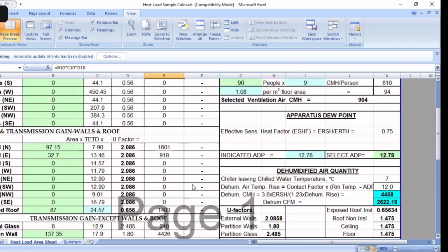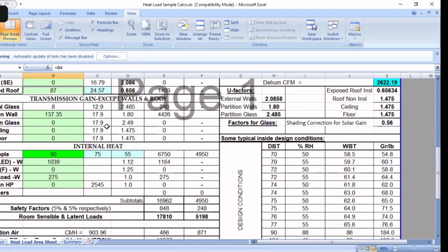So it was this wall. There was north and east side. North side wall, this is the area. East side wall, this is the area minus the glass wall. This is the area, and this is the TETD, and this is the U factor, this is the heat load, and exposed roof is there. Then the external wall, this much is the partition wall, this is the temperature difference of partition wall, this is the U factor, this is the heat load, so everything.